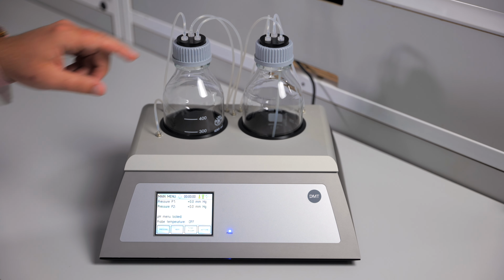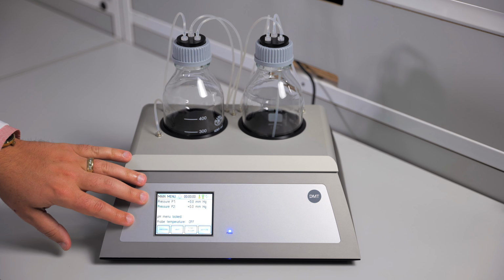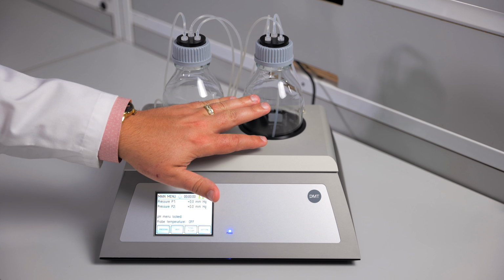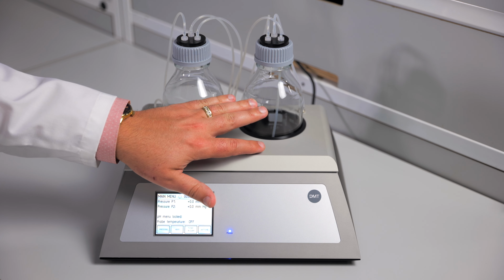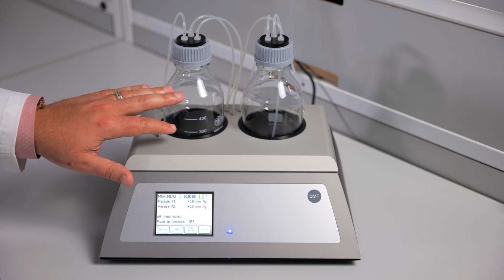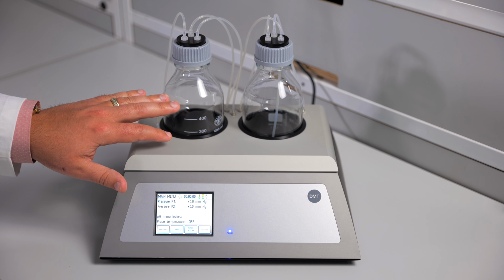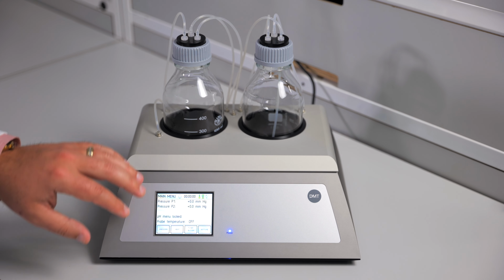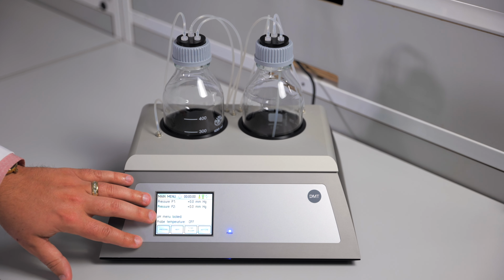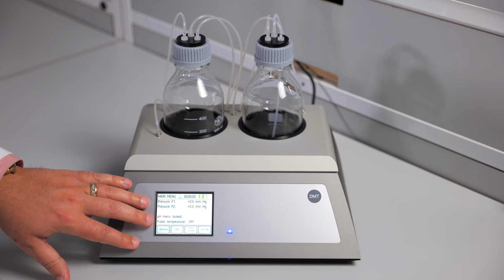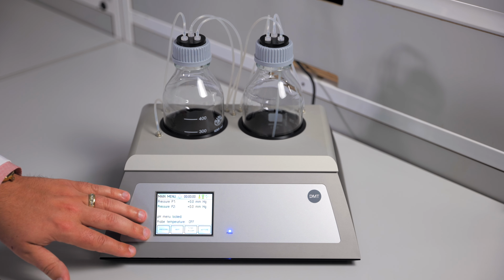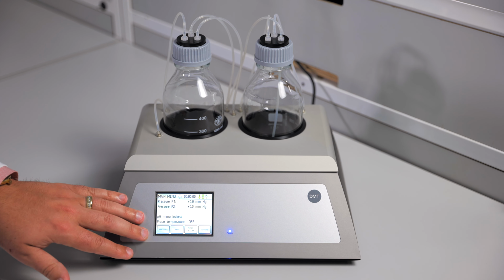The interface consists of two bottles and the touchscreen. One bottle will drive the pressure through your system. The second is a waste bottle that will collect anything that comes through the vessel. You also have your touchscreen interface, which can be used to control things such as temperature, pressure, flow rates, as well as running pressure calibrations.